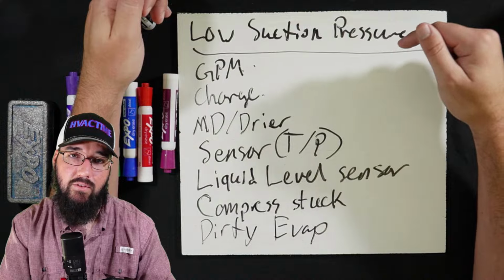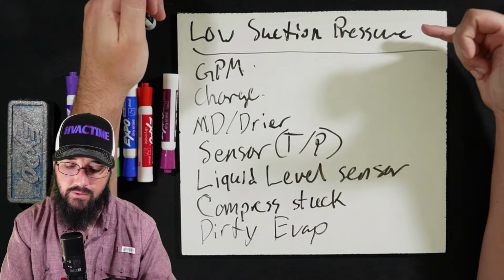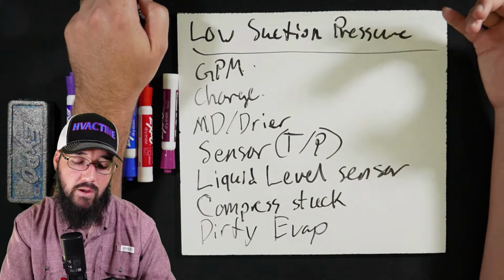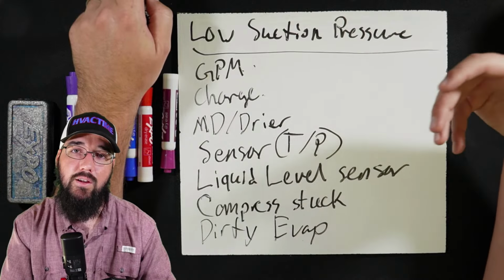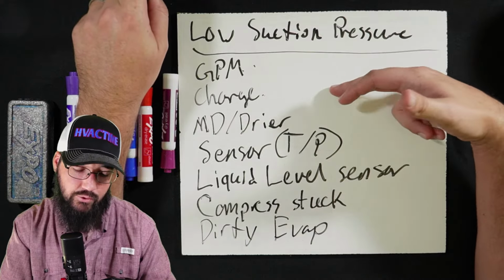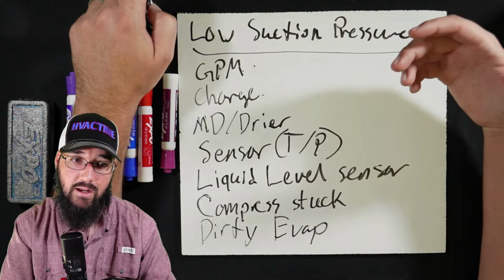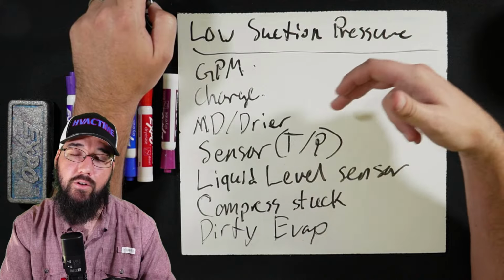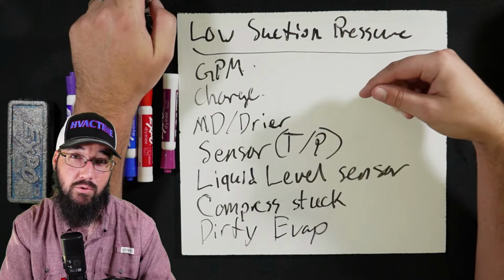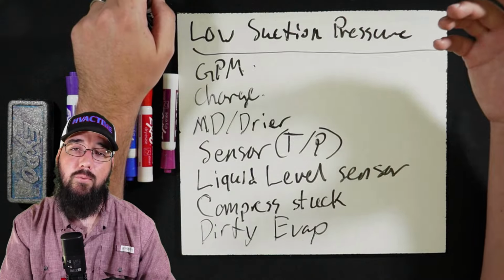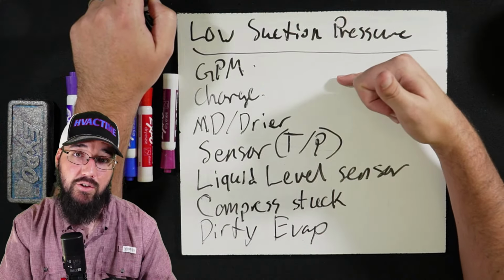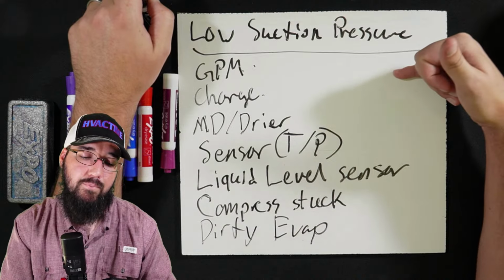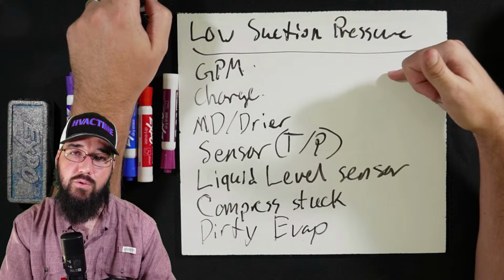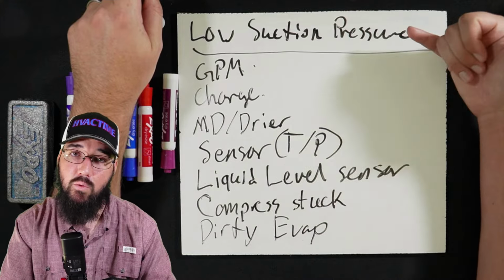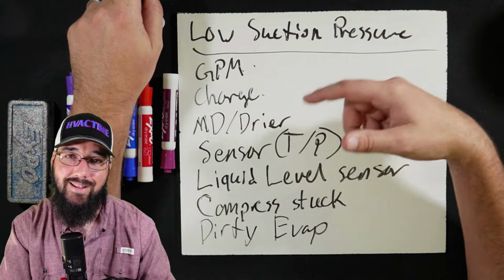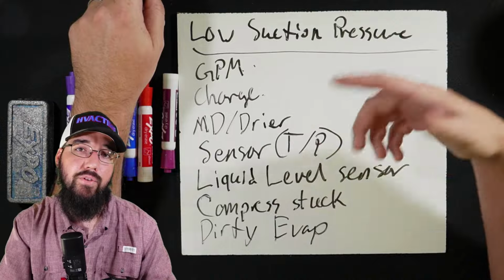The separator is not able to process all of that back out, and then it gets caught into the evaporator. That heavy oil charge will also cause low suction pressures, and you're going to see that through the approach values. You'll see high approach values if we have a low charge condition, an underfeeding of the evaporator of any kind, or a dirty evaporator. I would expect the approach on this machine to be less than 3 degrees. Approach is the difference between suction saturation and leaving water temperature. If it's more than that, it indicates a heat exchange issue, which plays into charge or underfeeding of the evaporator in some way.